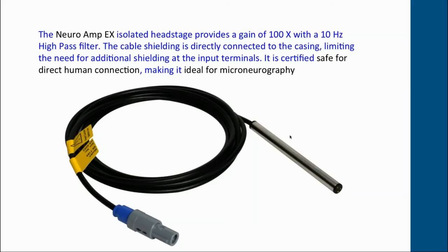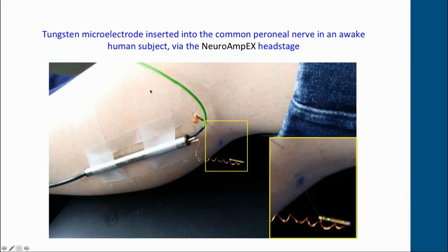This shows how we would attach the NeuroAmpEX to the leg of a subject. You can use a Velcro strap to wrap it around the calf, or simply tape it on. You don't need to put gel on the head stage — and in fact you shouldn't, because gel could enter the terminals and short circuit or even damage it.